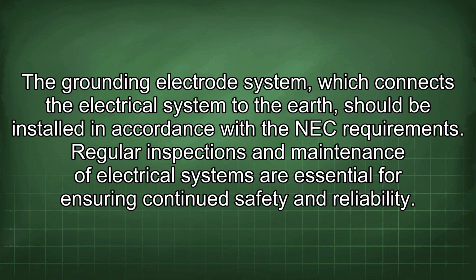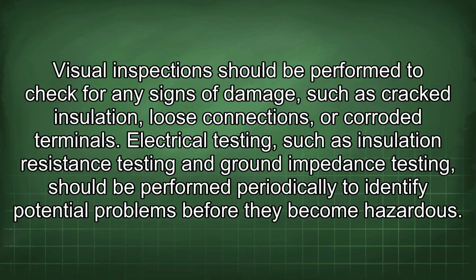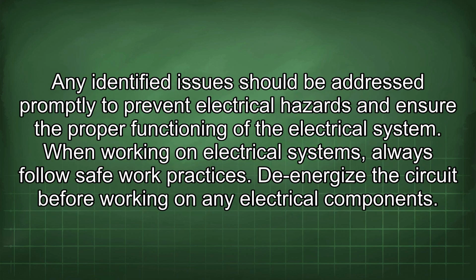Regular inspections and maintenance of electrical systems are essential for ensuring continued safety and reliability. Visual inspections should be performed to check for any signs of damage, such as cracked insulation, loose connections, or corroded terminals. Electrical testing, such as insulation resistance testing and ground impedance testing, should be performed periodically to identify potential problems before they become hazardous. Any identified issues should be addressed promptly to prevent electrical hazards and ensure the proper functioning of the electrical system.